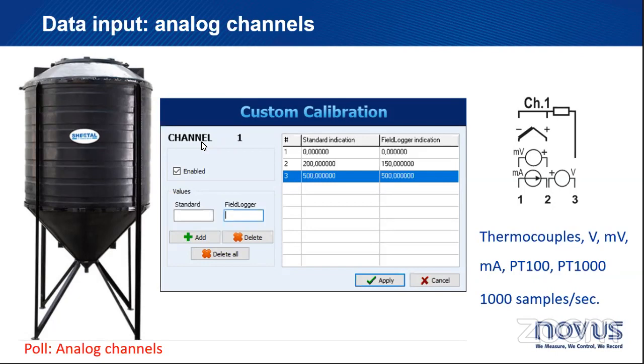You can select the inputs to be read at a frequency that is much higher than the frequency that you actually record data inside of the memory. What is the advantage? Well, the main advantage is you save some storage. I'll give you an example. Remember I mentioned more than once that FieldLogger is a nice option for a monitoring system. You might want to be monitoring something very quickly, but you might not want to record that quickly.